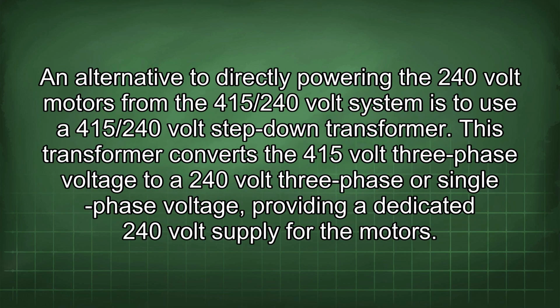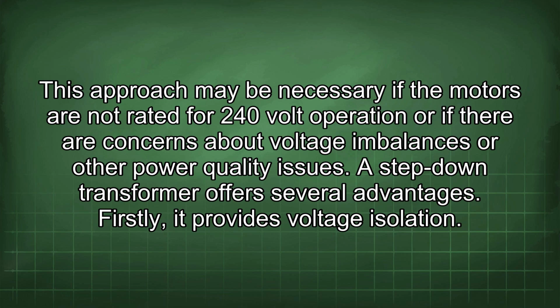An alternative to directly powering the 240-volt motors from the 415/240-volt system is to use a 415/240-volt step-down transformer. This transformer converts the 415-volt 3-phase voltage to a 240-volt 3-phase or single-phase voltage, providing a dedicated 240-volt supply for the motors. This approach may be necessary if the motors are not rated for 240-volt operation or if there are concerns about voltage imbalances or other power quality issues.